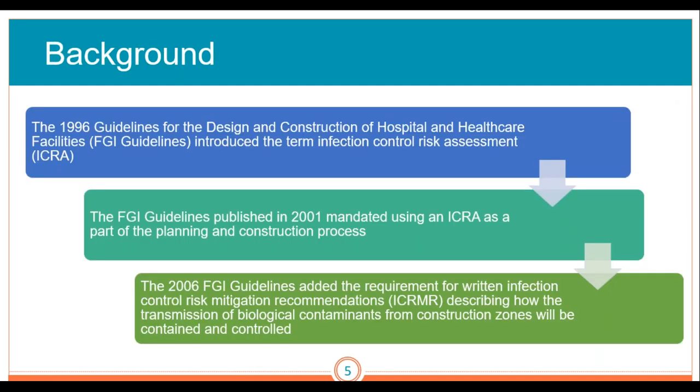So let's go through a little bit of the history and background. The 1996 guidelines for the design and construction of hospital and healthcare facilities introduced the term infection control risk assessment — the ICRA. The FGI guidelines published in 2001 mandated using an ICRA as part of the planning and construction process. In 2006, the FGI guidelines added the requirement for written infection control risk mitigation recommendations — the ICRMR — describing how the transmission of biological contaminants from construction zones will be contained and controlled. These are supposed to be renewed around every four years. The most recent ones are from 2018, but there are still a lot of people who are following the 2014 FGI guidelines.